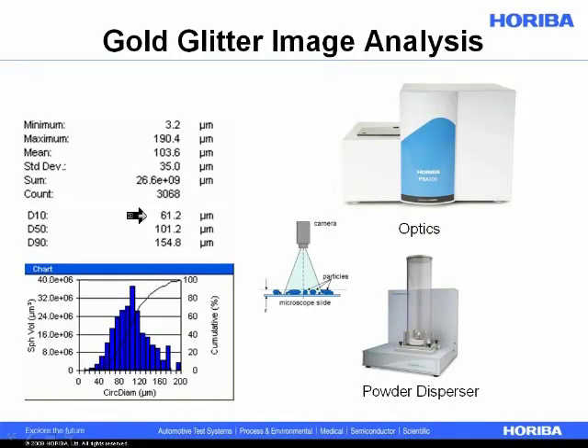In this case, we verified that the results from laser diffraction look accurate, because image analysis is the referee technique for particle size analysis. But in addition, we'll also get shape information — and perhaps when we're looking at glitter powder, the particle shape may be important.